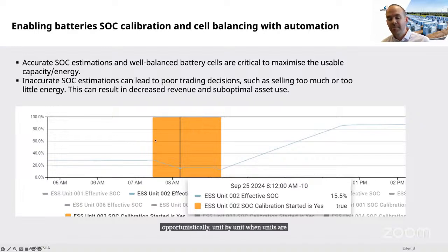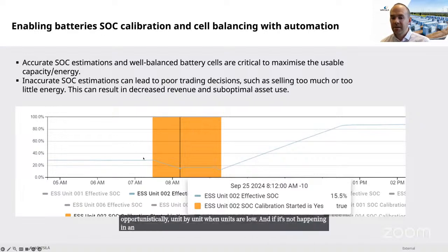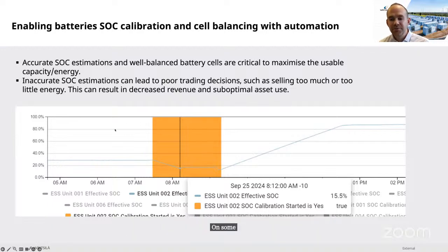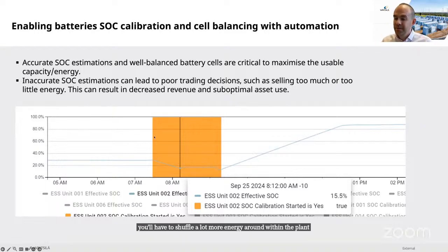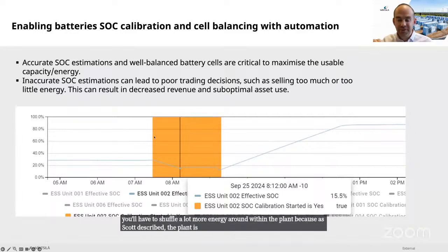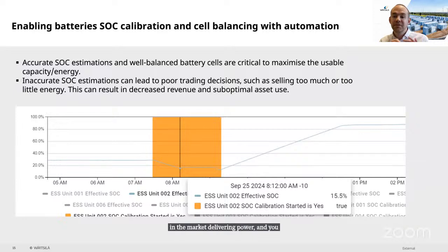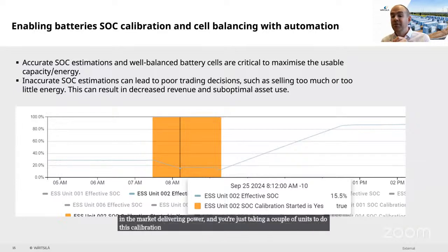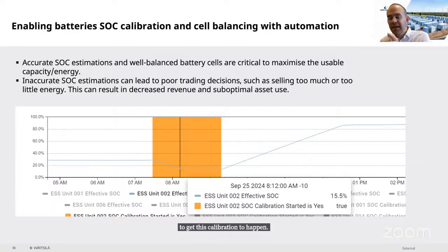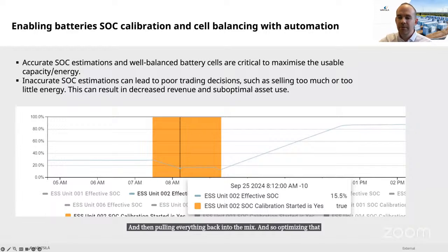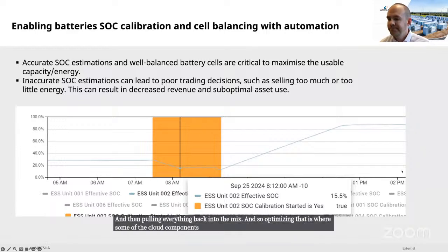And if it's not happening in an intelligent manner, if it's just happening on a clock, or on some predetermined schedule, you'll have to shuffle a lot more energy around within the plant, because as Scott described, the plant is in the market delivering power, and you're just taking a couple of units to do this calibration. You're shuffling energy around. We're intentionally moving the SOCs away from each other with automation to get this calibration to happen, and then pulling everything back into the mix. And so optimizing that is where some of the cloud components really come into play.